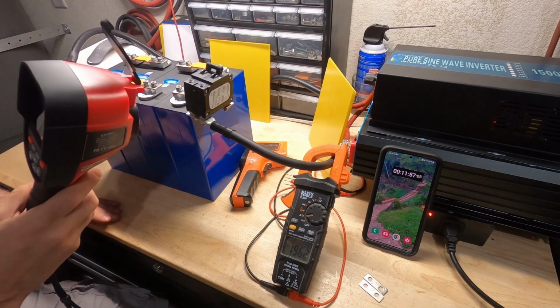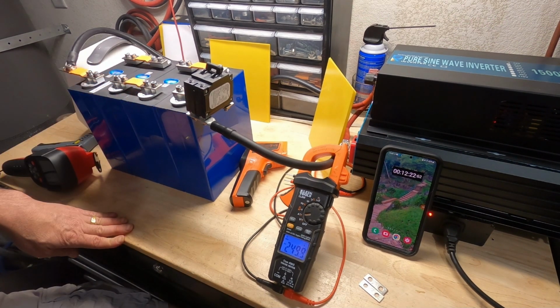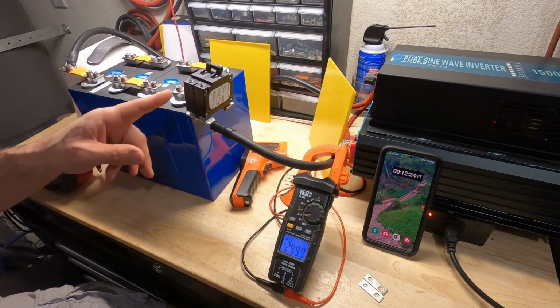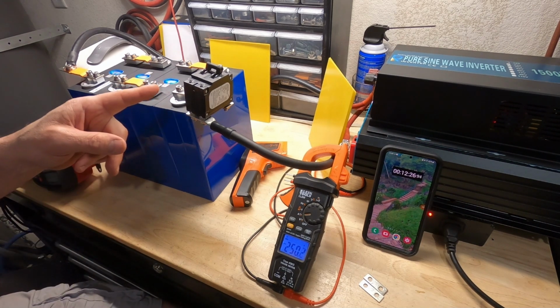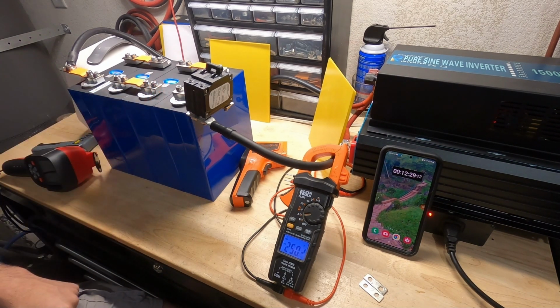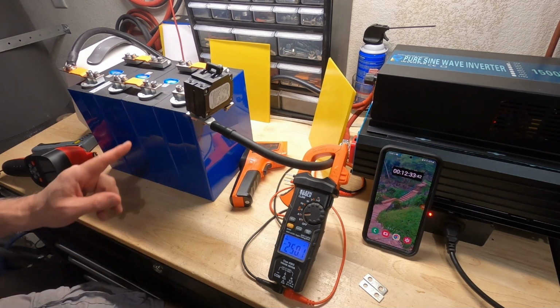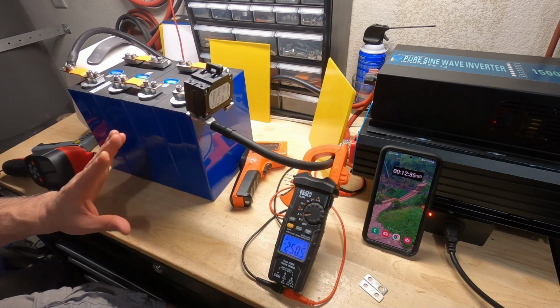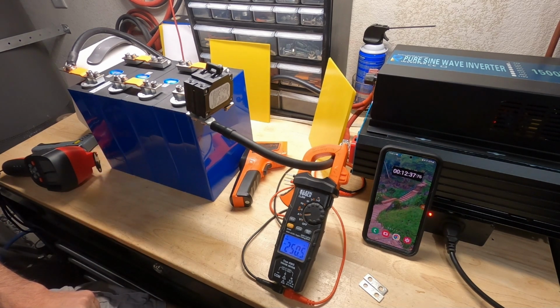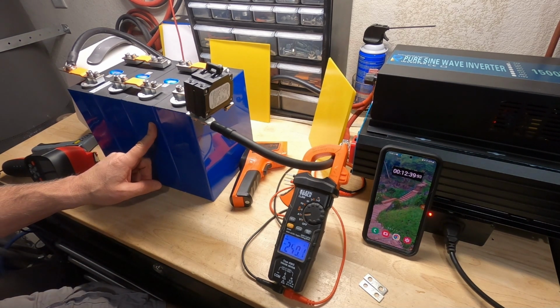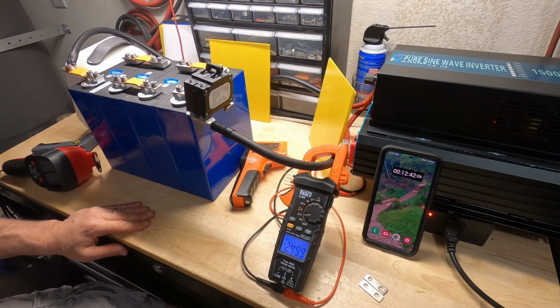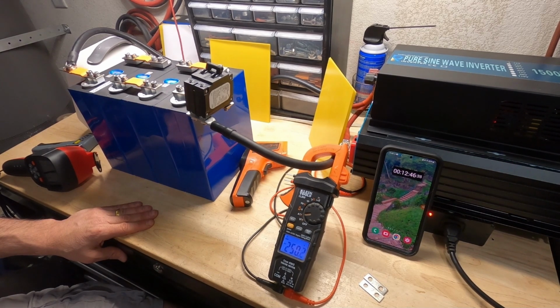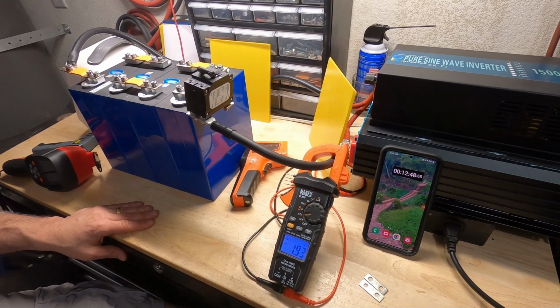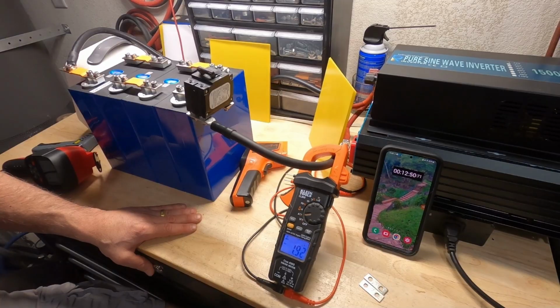Let's pop the breaker. Turn it up to 250 amps. See if we can pop the breaker. Takes about 30 seconds at this rate. Makes me nervous. We're pushing these cells at about 1 C rate. These are 280 amp hour cells. We're pushing 250 amps. There it goes. So the breaker's still working.